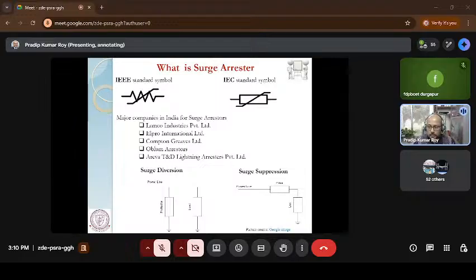And I can say Crompton is the first company in India that introduced a 1200 kV transformer, in 2012. Earlier, the transformers used were around 600 to 800 kV. Then they started 1200 kV and more than that. But to protect that equipment, they started the development of this surge arrestor. That development is what I'm talking about here.